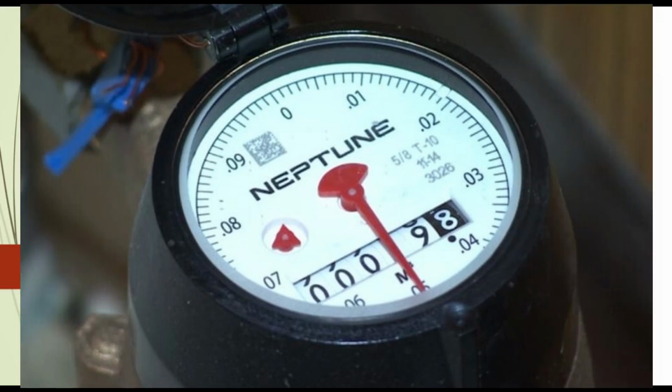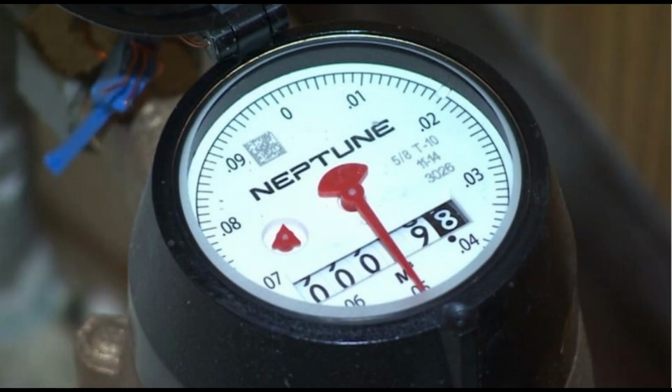Multi-jet meters generally have an internal strainer element that can protect the jet ports from getting clogged. Multi-jet meters normally have bronze alloy bodies or outer casings, with internal measuring parts made from modern thermoplastics and stainless steel. Turbine meters are less accurate than displacement and jet meters at low flow rates, but the measuring element does not occupy or severely restrict the entire path of flow.